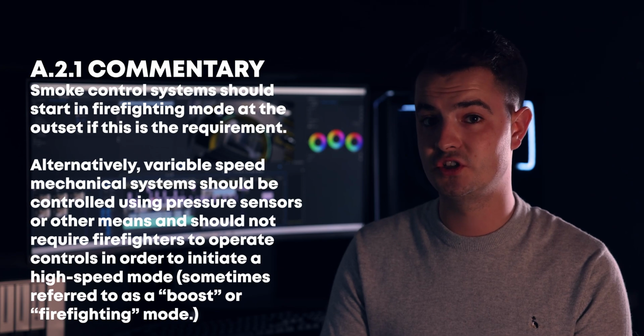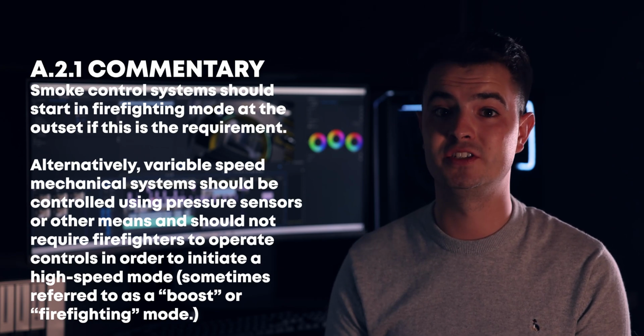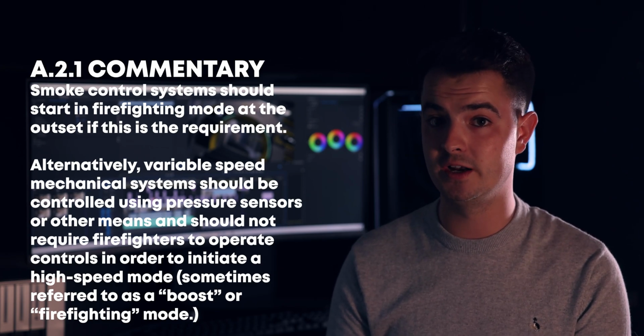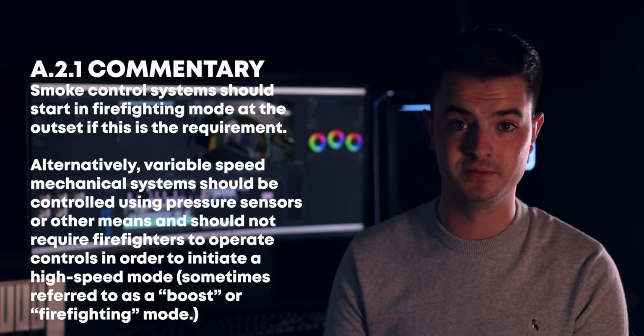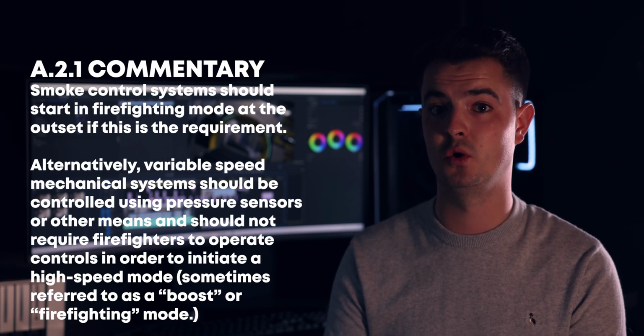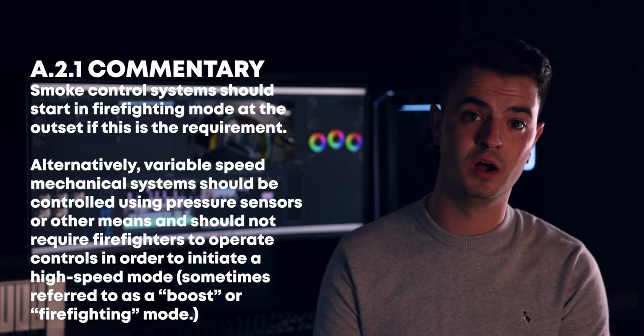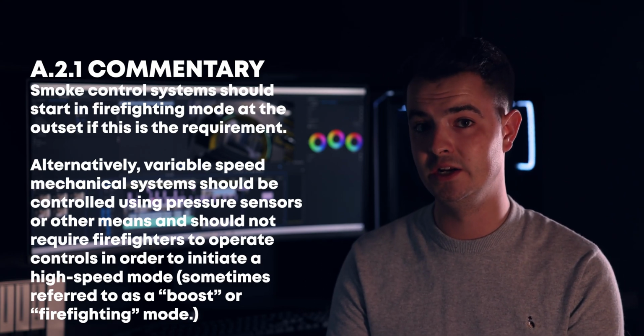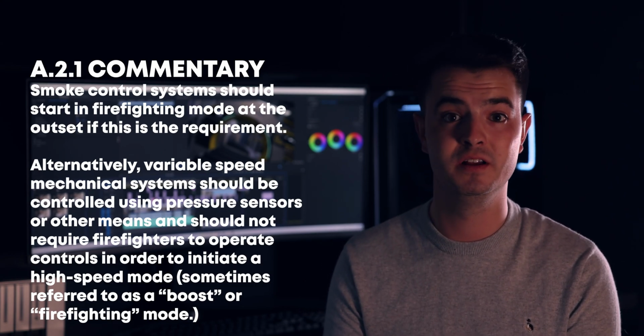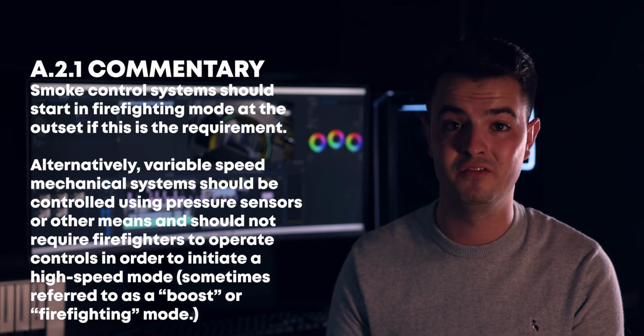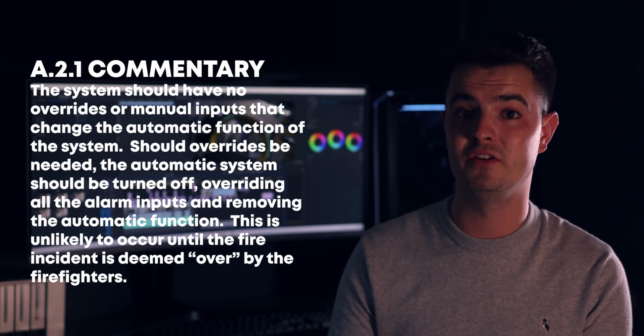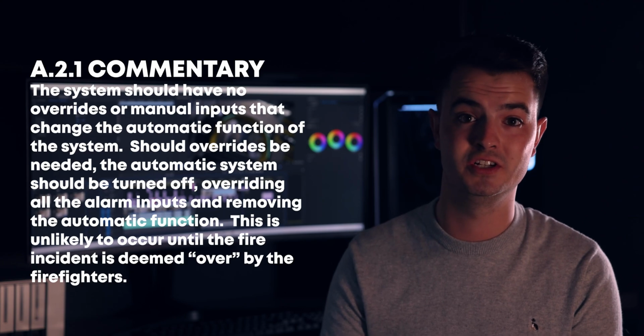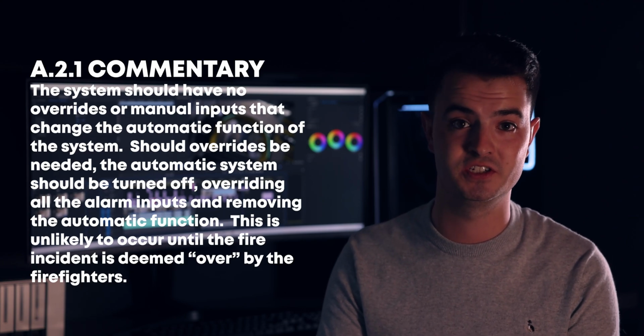Smoke control systems should start in firefighting mode at the outset if this is the requirement. Alternatively, variable speed mechanical systems should be controlled using pressure sensors or other means and should not require firefighters to operate controls in order to initiate a high speed mode, sometimes referred to as boost or firefighting mode. The system should have no overrides or manual inputs that change the automatic function of the system.